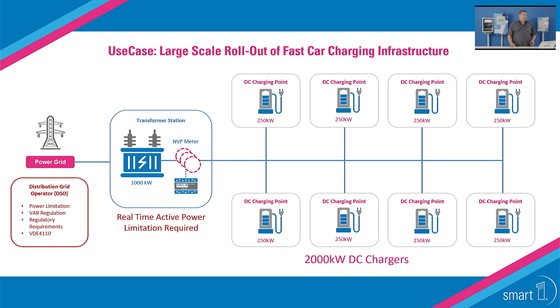So switching back into the actual project that we were just in, the way this works is that the client first of all needs to install measurements. So what they do is they install on the grid connection point a meter that measures the power in real time. The next thing the client does, inside the transformer station, they install our EASY2 e-mobility box. What they then do is they wire each of the chargers directly to that e-mobility box. So you will have an Ethernet connectivity going to this e-mobility box.